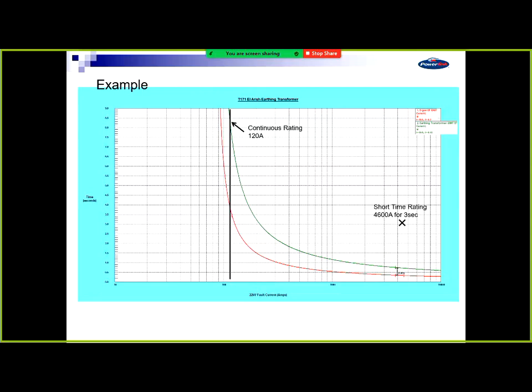You can use those formulas for the standard inverse in Excel or any sort of program, in MathCAD, any sort of application like that, to do this. Someone internally wrote this in the 90s, so a very long time ago, before Excel was even around. This is actually a substation in far north Queensland. So you can see what's on the left-hand side, the line straight up, is the continuous rating. The red line is the Ergon IDMT curve, and the green line is our curve. So you see at the maximum fault level of 3,820, although it's hard to pick up on that log scale, we have a 400 millisecond gap. And it's hard to read, but you can see a time multiplier setting in the green of 0.43.